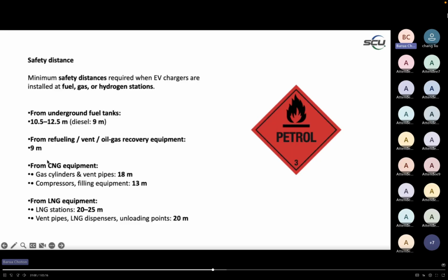But if it's a CNG station, then from the gas cylinders and vent pipes, it is recommended to install 18 meters away. From the compressors and filling equipment, it is recommended 13 meters. If we look at the LNG equipment, more distance is required. From the LNG stations, we need to keep a distance of at least 20 to 25 meters. And from the vent pipes, LNG dispensers, or unloading points, it is recommended to have 20 meters distance. So these are all the safety distances to install an EV charger into a petrol station.